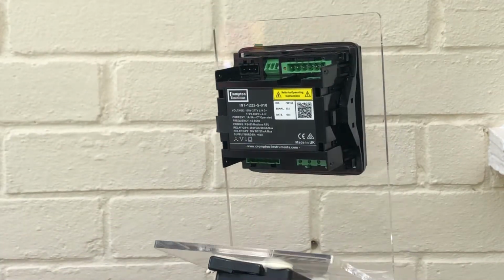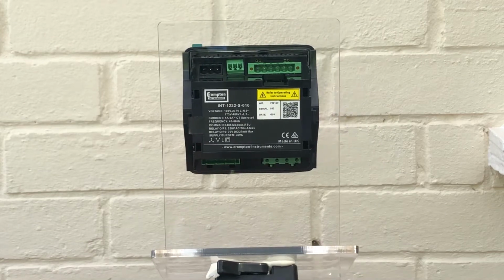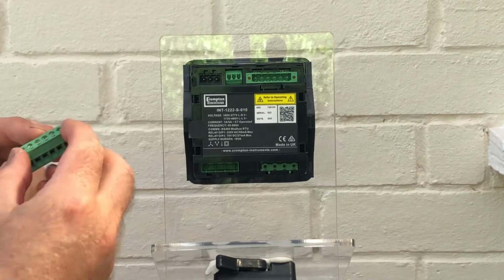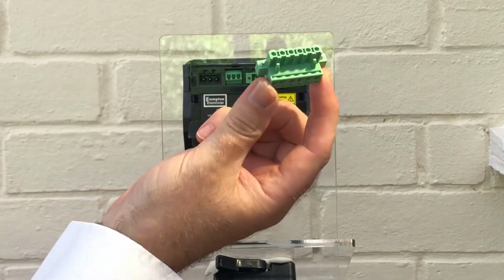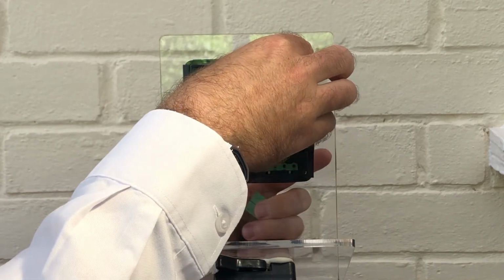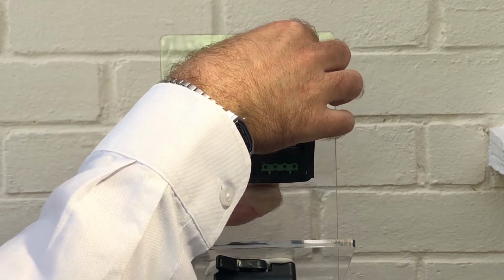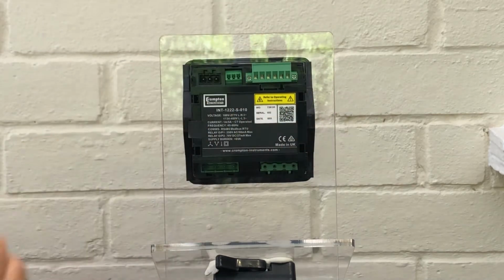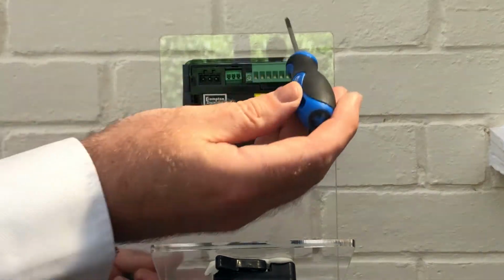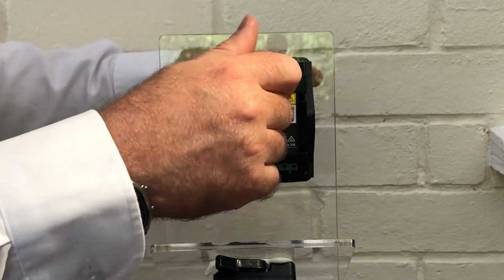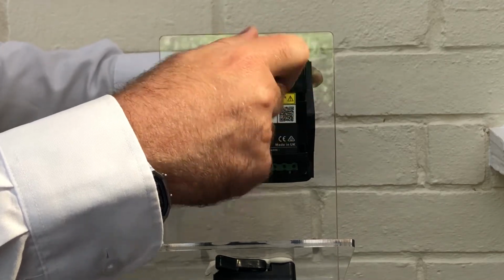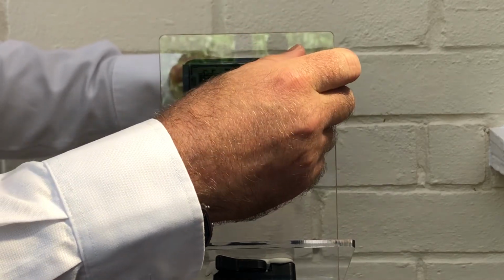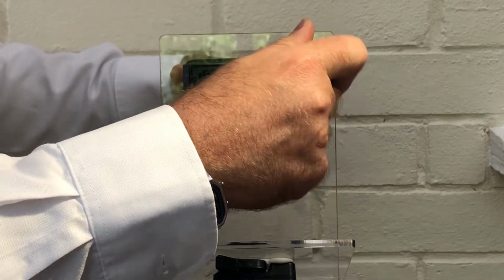Next, we're going to fit the terminal blocks for voltage, current, Modbus and pulsed outputs. The first terminal block is the current terminal block, which fits into the top of the product. For safety reasons, we advise screwing the current terminal block securely into place to avoid accidental removal of the current connection.